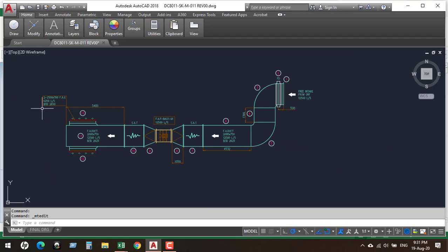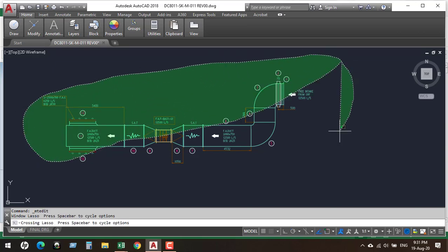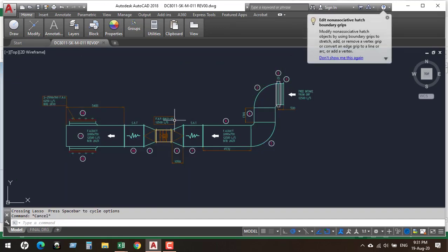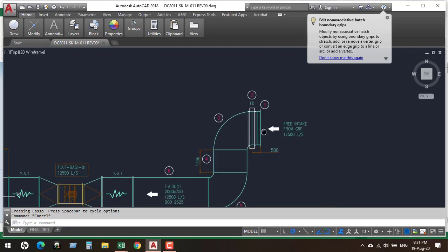Now also you need to be familiar with the ASHRAE fitting designation, what fittings are available in the ASHRAE duct fitting database. So you need to spend some time to get familiar with the fittings and the code of the fittings. I have done this calculation many times, so I'm a bit familiar with these fittings. So we'll go straight to the calculation.